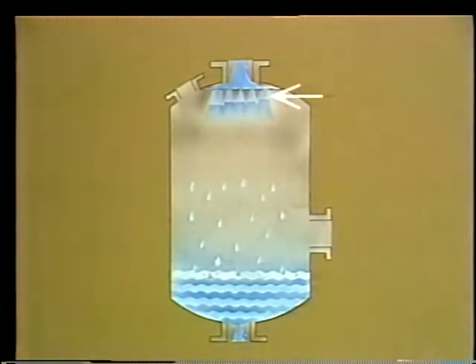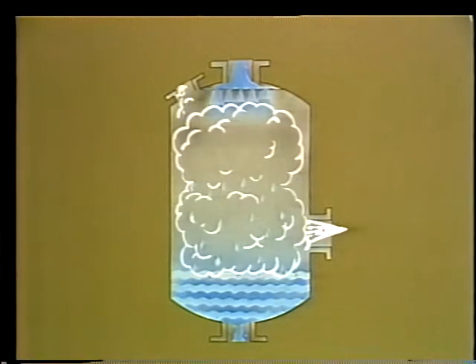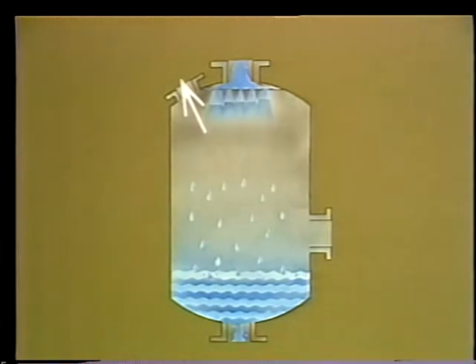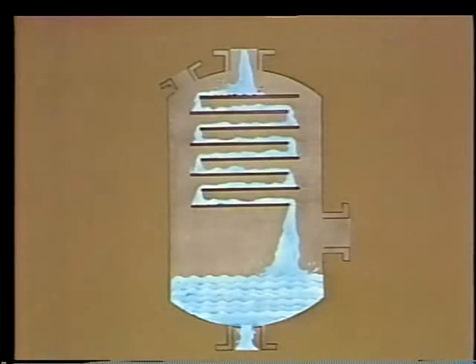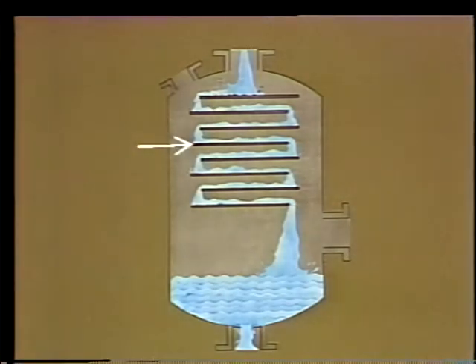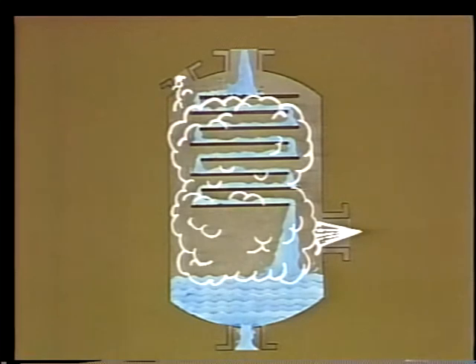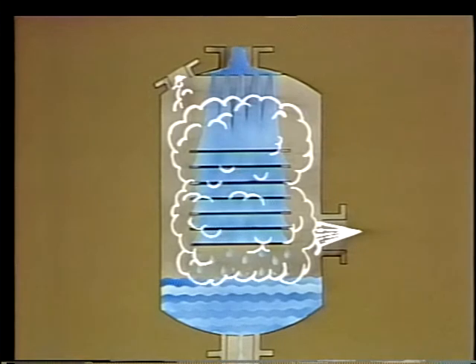A spray de-aerator sprays the incoming feed water down through a steam-filled space where air and gases which can't be condensed are scrubbed away by the live steam. The air and other gases are vented either to open air or to a condenser. In tray de-aerators, the feed water cascades over a set of trays while steam heats it up and strips it of the non-condensable gases. The third type combines both the spray and the tray designs for even greater efficiency and capacity.